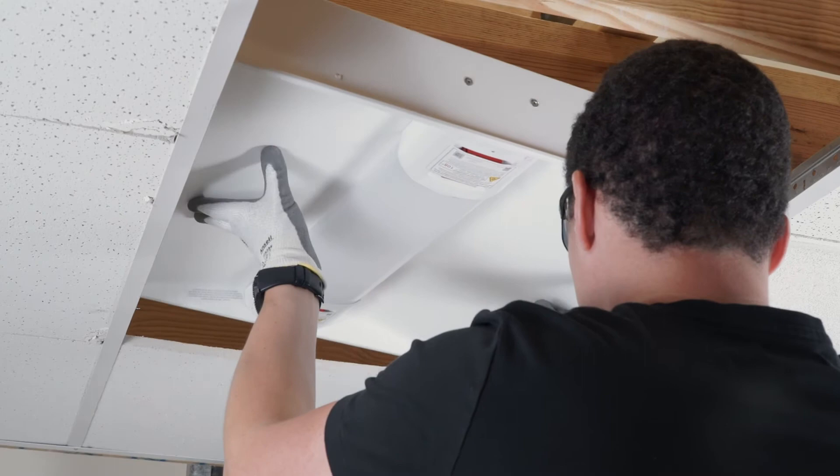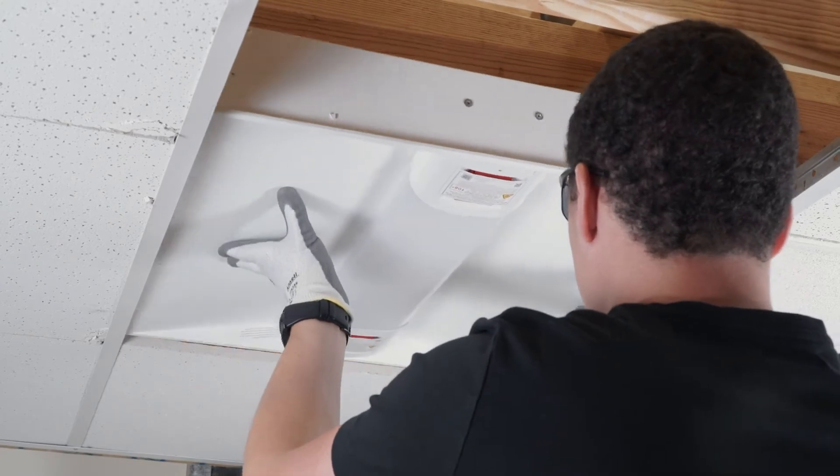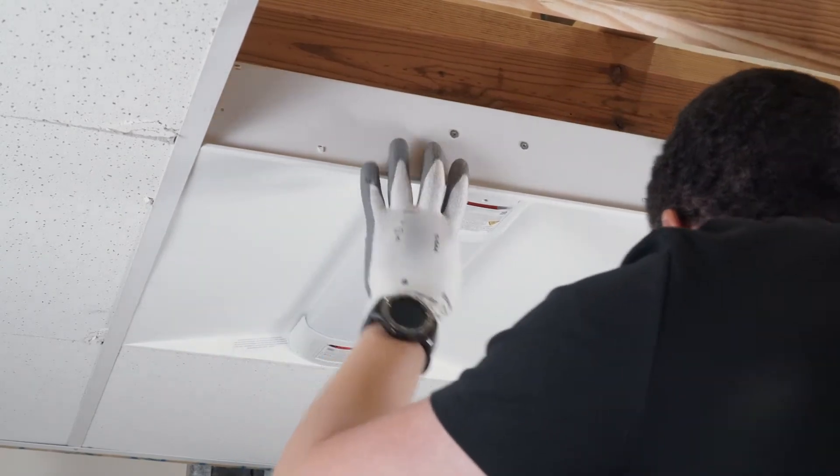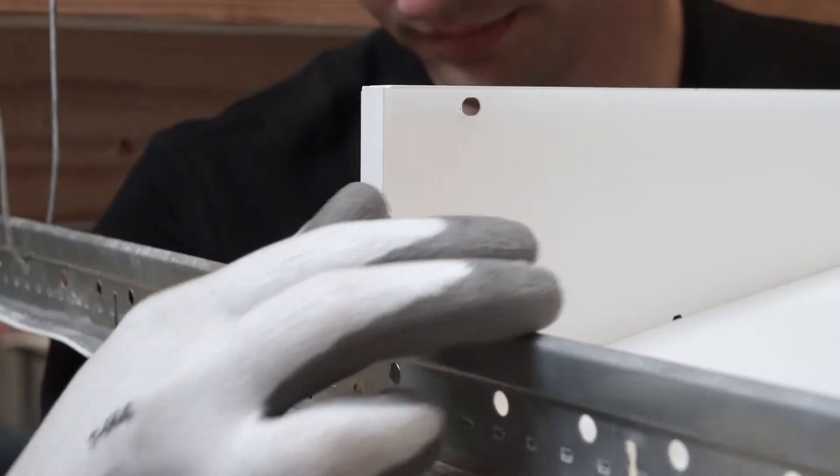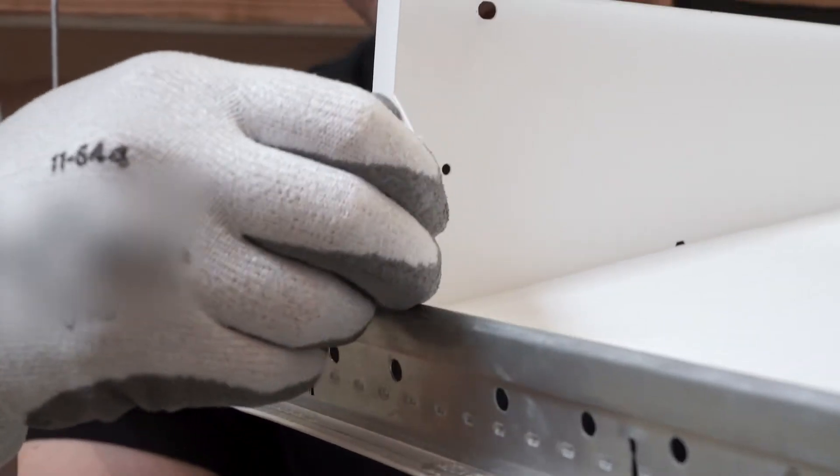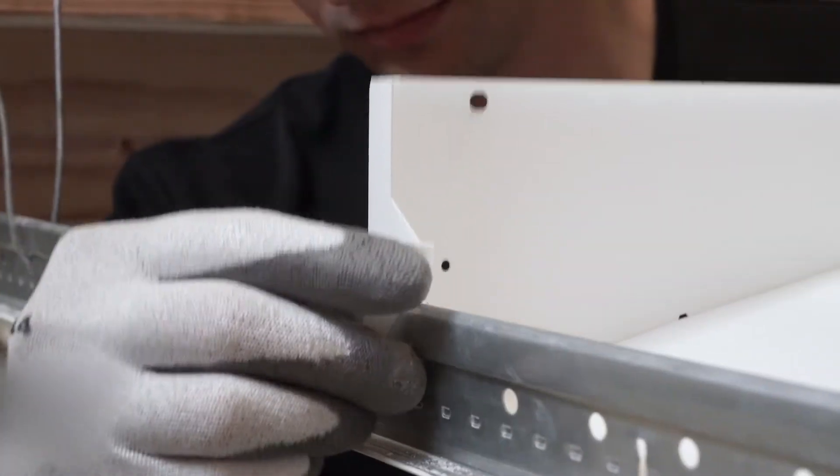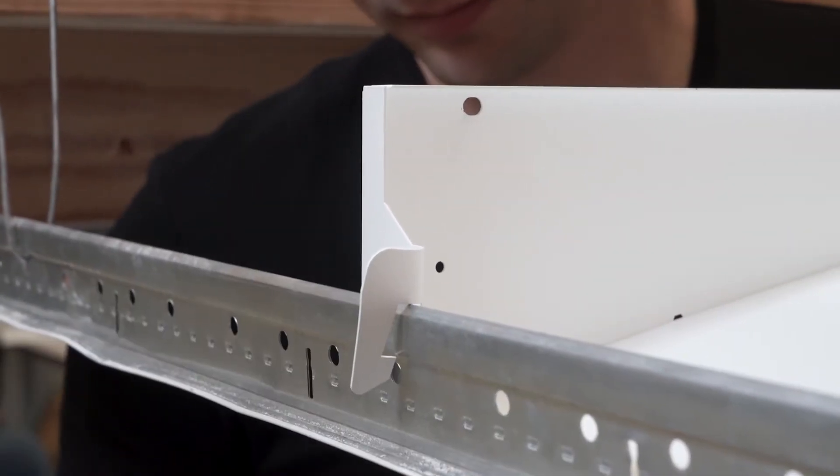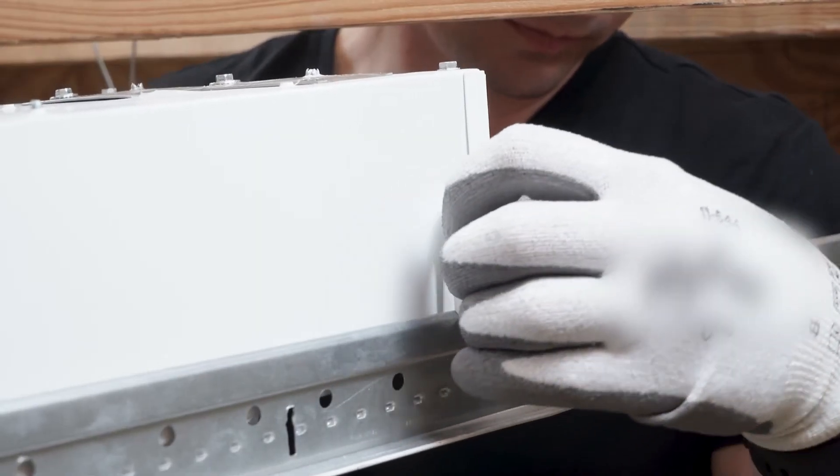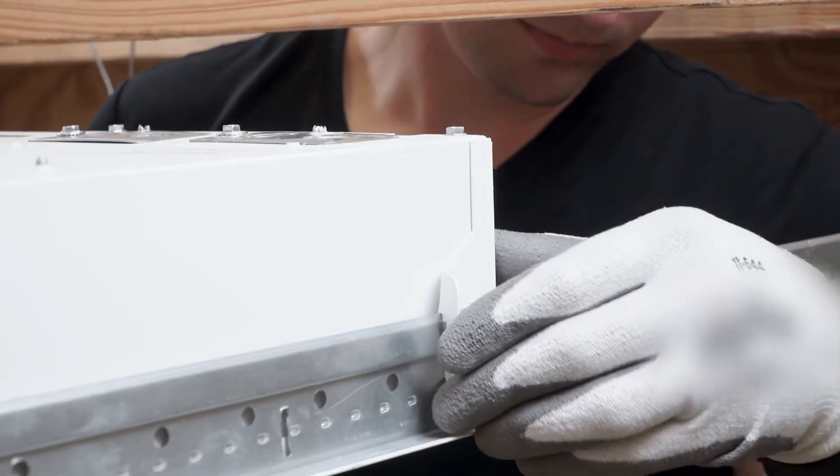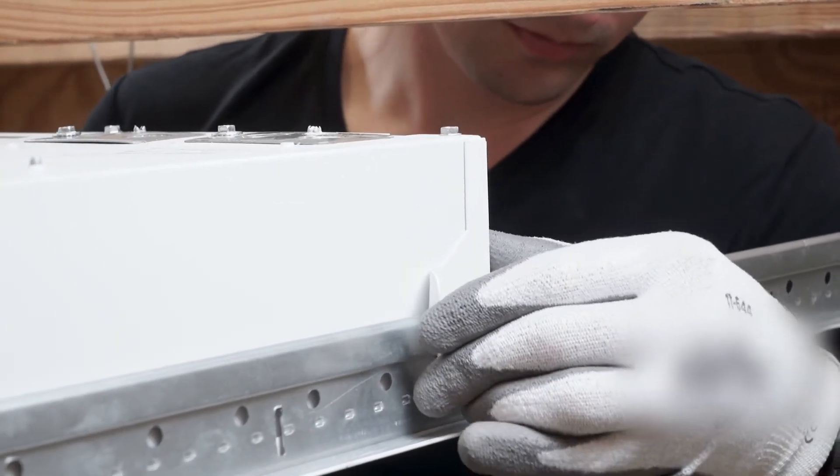First, install the fixture in a T-grid ceiling opening. Once the fixture is in place in the grid, secure the troffer to the T-bars by bending the built-in clips on all four corners of the fixture so they secure to the T-grid.